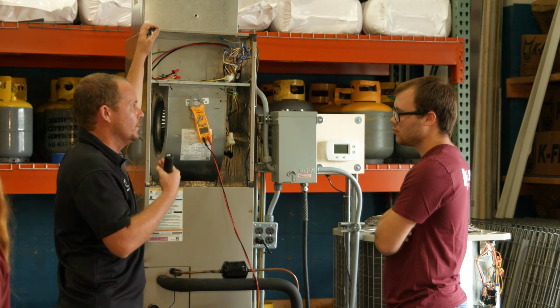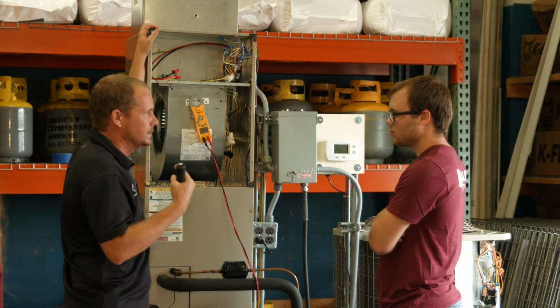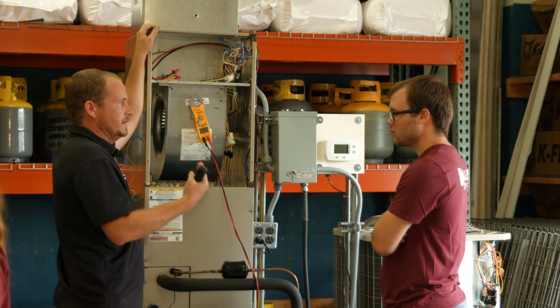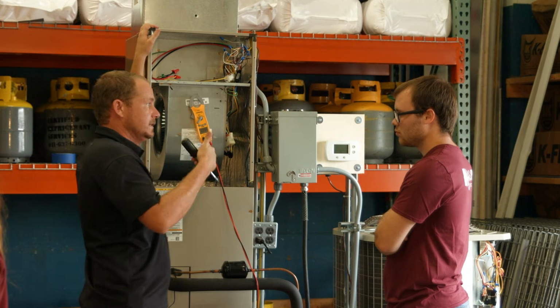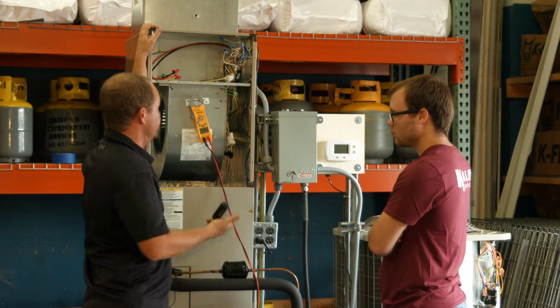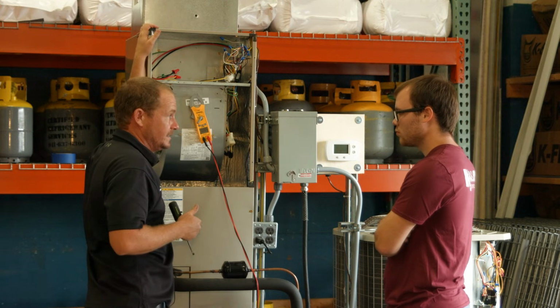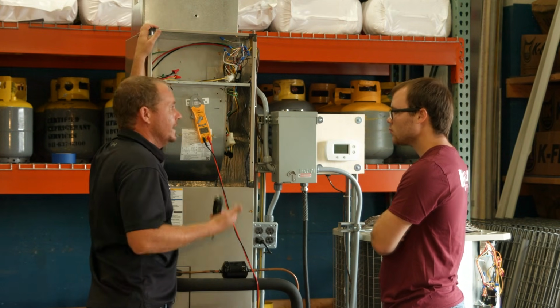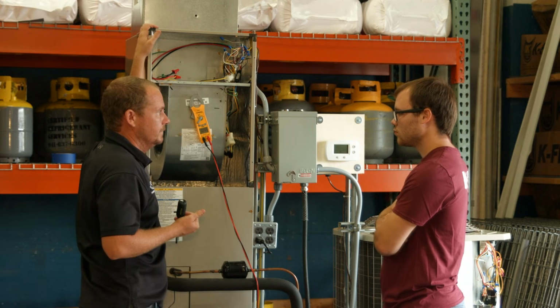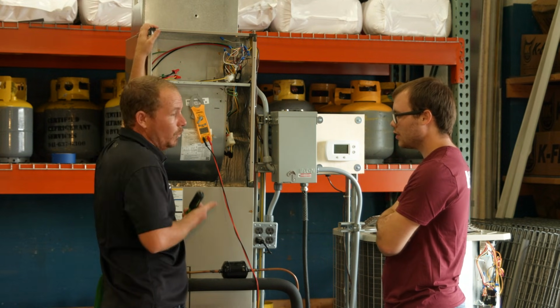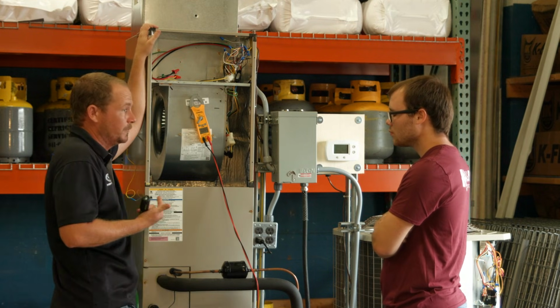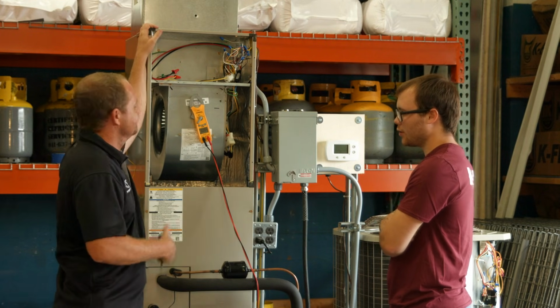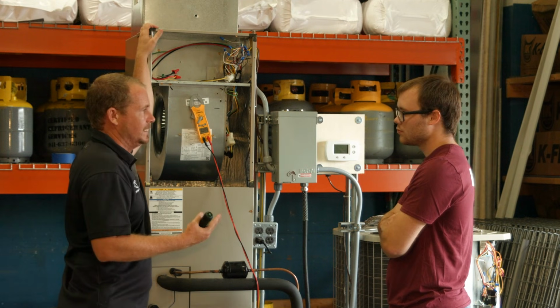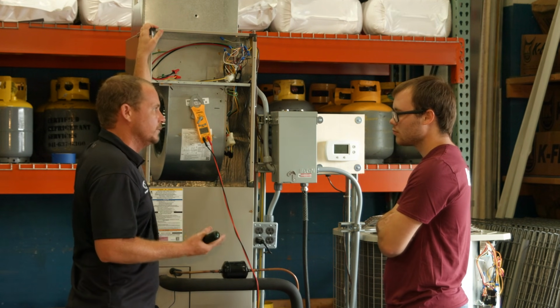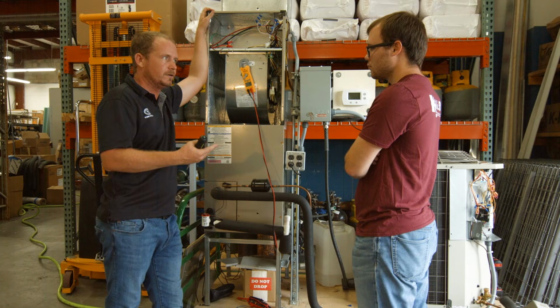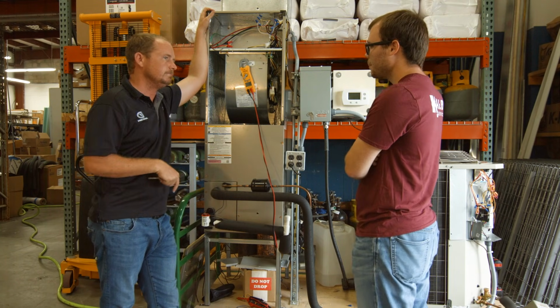Could be programmed wrong. There's a wide range of visual and just sensible things you'd want to go through first to make sure. You'd want to look and see, is the coil attached to the reversing valve? Like you mentioned, do I have poor connections in obvious areas? Do all those first, and then pull out your meter and confirm, do I actually have 24 volts? Or you can do it the other direction, whichever way you prefer. I always prefer, especially for newer techs, start with visual, start with everything you can check, and then don't be afraid to pull your meter out, but don't lead with your meter. Okay. All right, so go ahead and do that.